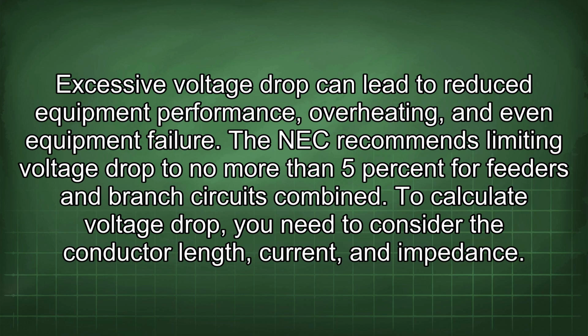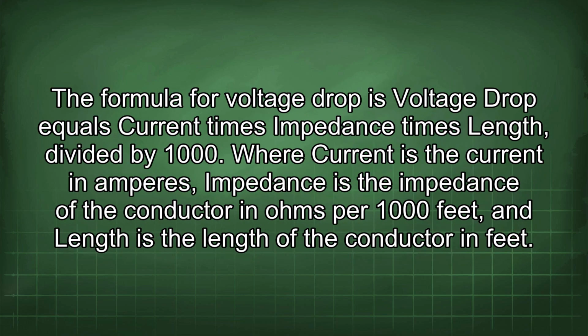To calculate voltage drop, you need to consider the conductor length, current, and impedance. The formula for voltage drop is voltage drop equals current times impedance times length, divided by 1000. Where current is the current in amperes, impedance is the impedance of the conductor in ohms per 1000 feet, and length is the length of the conductor in feet.